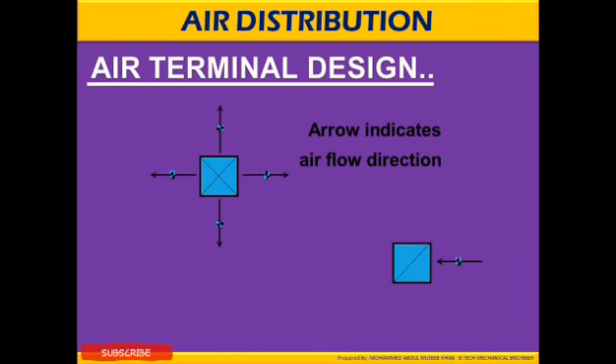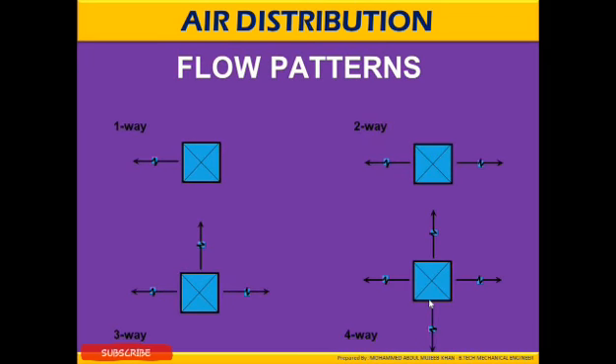Air terminal designs, airflow indications and directions. This is a typical example of a supply air diffuser or the supply air duct, and this is an example of a return or an exhaust air duct. Flow pattern. The diffusers are classified into basically 4 patterns, which is known as one-way, two-way, three-way and four-way, which simply indicates the flow of air in the directions. One-way diffuser is only directed one way, and by the name itself, two-way, three-way and four-way are the directions of the air terminal's flow pattern.